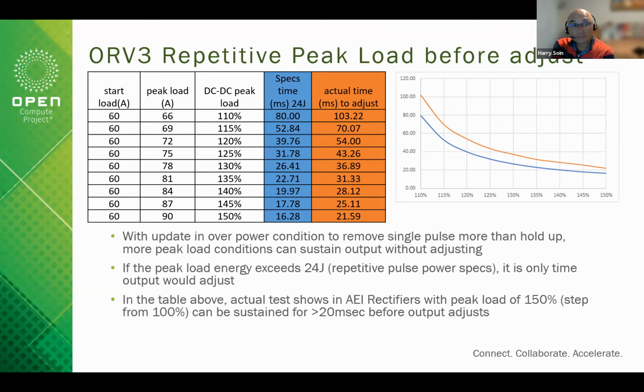All in all, up to 150% of the load, stepping from 100%, we can get greater than 20 milliseconds of hold-up time before any adjustment, before the output ever adjusts. And the condition here, like I mentioned, the spec is 24 joules. Instead of focusing on time, we're focusing on the energy level of 24 joules, and we've designed with 30 joules in mind so we have margin in place for these conditions.